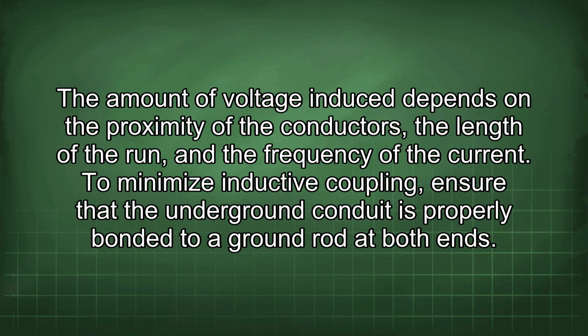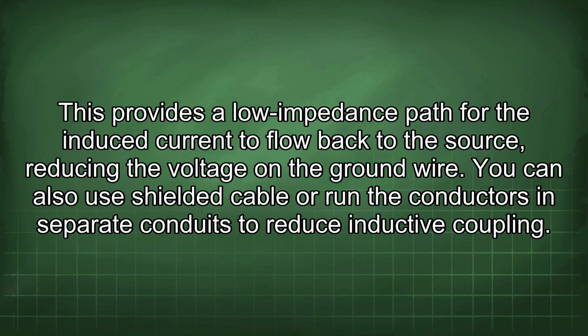of the current. To minimize inductive coupling, ensure that the underground conduit is properly bonded to a ground rod at both ends. This provides a low impedance path for the induced current to flow back to the source, reducing the voltage on the ground wire.